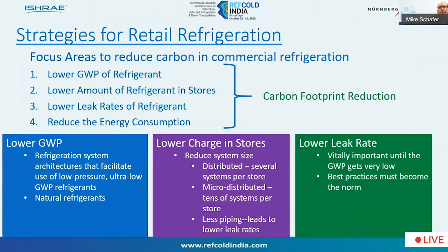So the 3 strategies we'll focus in on predominantly would be the lower GWP, selection of the refrigeration architecture to utilize a low GWP refrigerant, certainly looking at natural refrigerants as a very good choice. And then in terms of lowering the charge in the stores, some of the system architectures are suitable for lowering the charge, and that would include the distributed, microdistributed systems. And all those lead to less piping in the store, which ultimately would lead to lower leaks. And then there obviously has to be a big focus on lowering the leak rate. That includes best practices, and trying to manufacture hermetically sealed units.